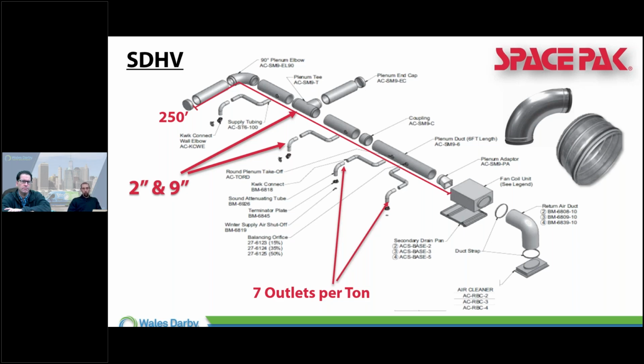We can, without new boards, basically pick a static pressure we want to be at, so we have some flexibility there based on how many outlets are in the space. Can we drop the airflow down a little bit more leniently when we talk about the water side? When we start getting into refrigerant, we don't want to freeze coils and stuff like that. So we need that proper airflow. It's still the basis of refrigeration, need airflow. Absolutely.